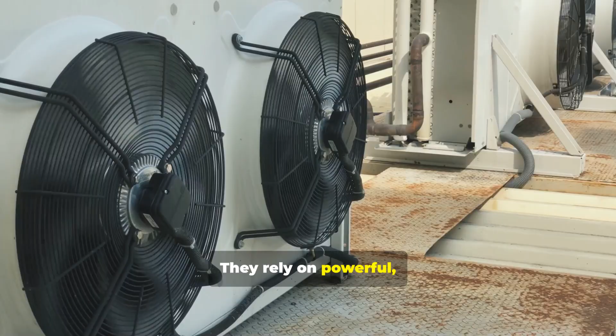On the surface, operators fight ambient air temperatures that can fluctuate by 30 degrees Celsius or more. They rely on powerful, energy-intensive mechanical chillers and air conditioning systems to maintain server temperatures around 20 to 25 degrees Celsius. Those systems can consume 30 to 40% of a data center's total power. Underground, the baseline is much closer to the desired state, dramatically reducing required energy.